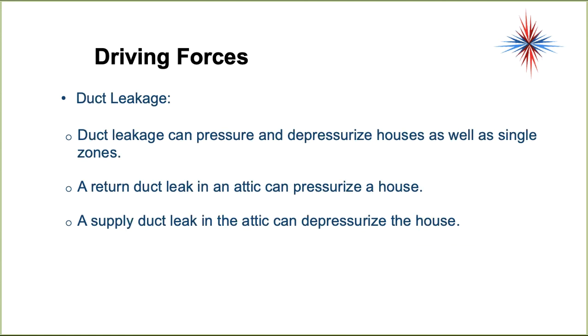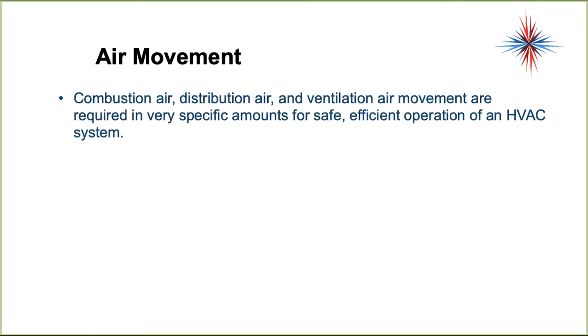Duct leakage can pressurize and depressurize houses as well as single zones. A return duct leak in an attic can pressurize a house; a supply duct leak in the attic can depressurize a house. Combustion air, distribution air, and ventilation air movement are required in very specific amounts for safe operation of any HVAC system — not just air conditioning, but heating as well.